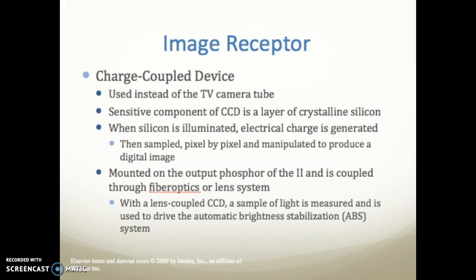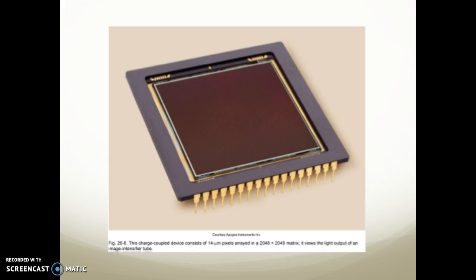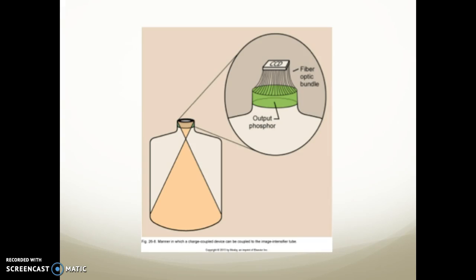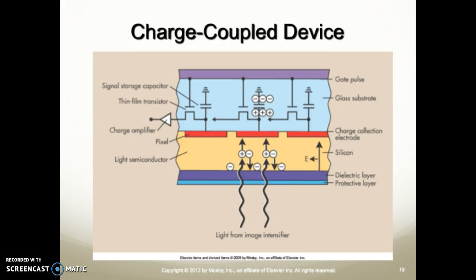The image receptor in digital fluoroscopy is a charge-coupled device (CCD), used instead of a TV camera tube. Its sensitive component is a layer of crystalline silicon. When silicon is illuminated, electric charge is generated, then sampled pixel by pixel and manipulated to produce a digital image. It is mounted on the output phosphor of the II and coupled through a fiber optic or lens system. With a lens-coupled CCD, a sample of light is measured to drive the automatic brightness stabilization system.